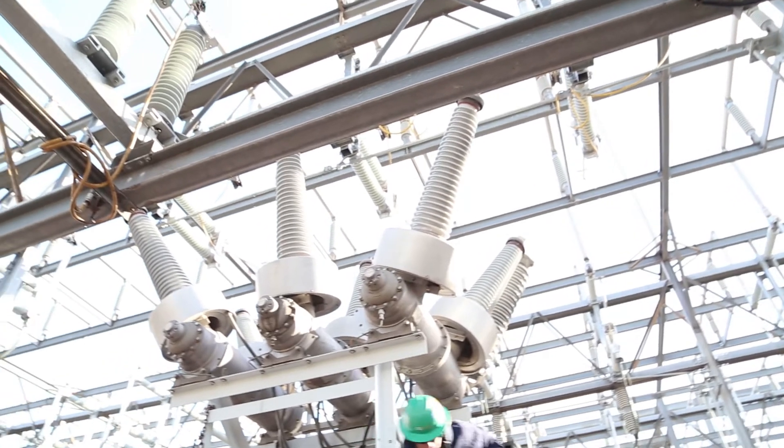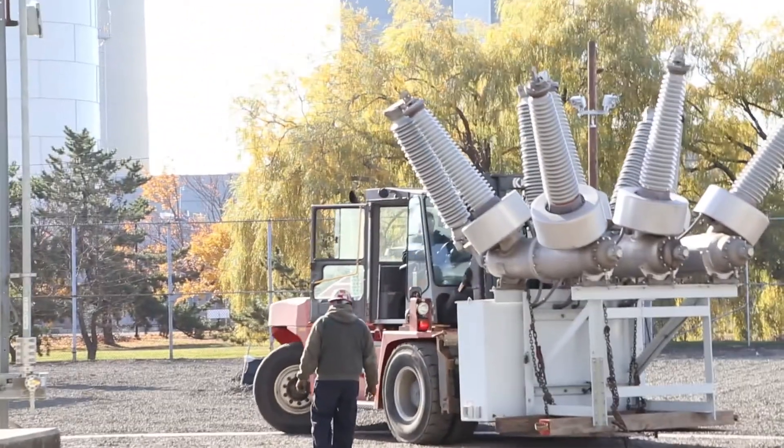The most complex part of this project was the ability to keep the substation energized while we were doing construction. We utilized low headroom pile driving rigs, and also we slid the transformers and PDCs in.